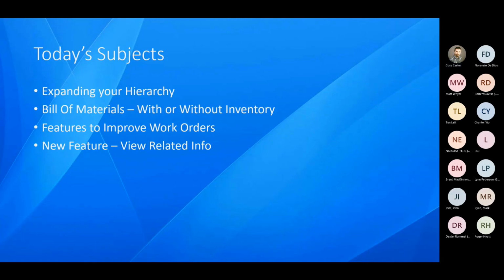A lot of people, and probably most everyone who is here, since most of you are coming from a hospital or a school background or school system, you probably don't have a spare parts inventory in the system. That's just me speaking from the experience of working with many clients. Most schools and hospitals don't necessarily keep a well-stocked parts room. But that does not mean that you cannot use the bill of materials functionality on the equipment or in the asset module, because you can. There is still a lot of benefit to using it, and I'm going to show you a way that you can use it without setting up a full inventory module.